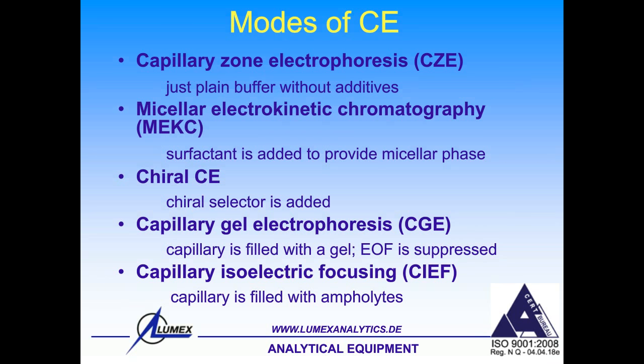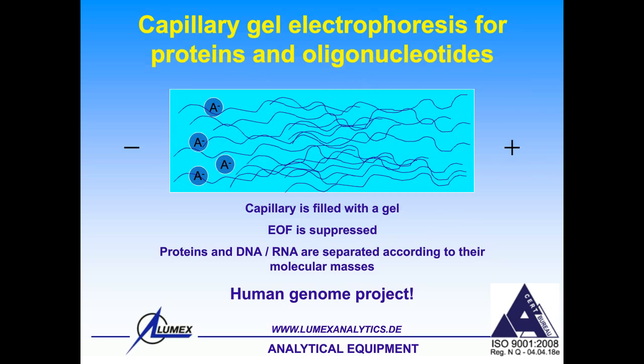The two most important modes for protein analysis are capillary gel electrophoresis, or CGE, and capillary isoelectric focusing. In capillary gel electrophoresis, the capillary is filled with a gel — not a cross-linked gel like SDS-PAGE slab gels, but a linear polymeric solution that is highly viscous. You need to apply a special high-pressure mode to fill the capillary with this gel. Electroosmotic flow is completely suppressed because the viscosity of the solution is very high.